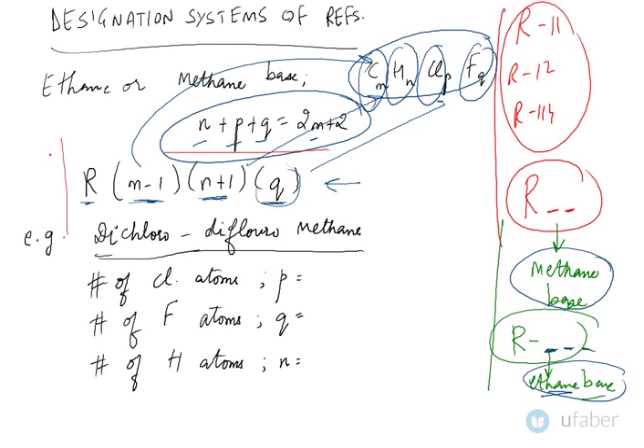This is the general rule by which we designate a system of refrigerants: R(M-1)(N+1)Q, where M is the number of carbon atoms, N is the number of hydrogen atoms, and Q is the number of fluorine atoms.